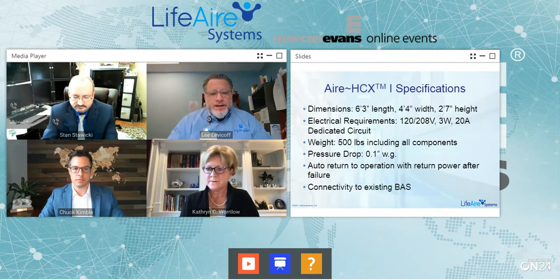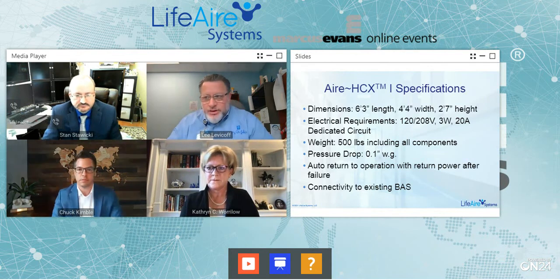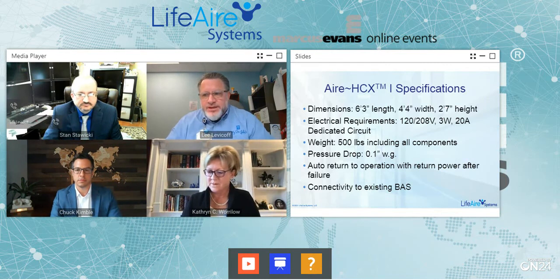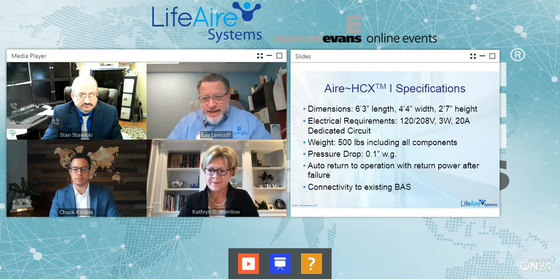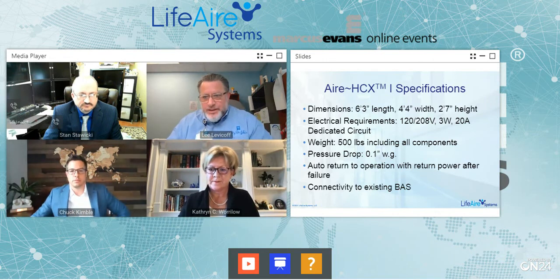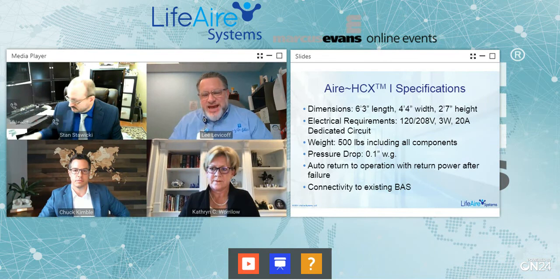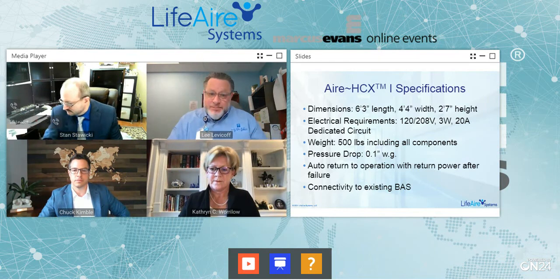The electrical requirements are something you've already got in the hospital — you're not bringing something from your transformers 700 feet away wondering how you'll get it there. You'll have power available: it's 120/208, a 20 amp dedicated circuit. So in most cases, it plays into the plug-and-play model.